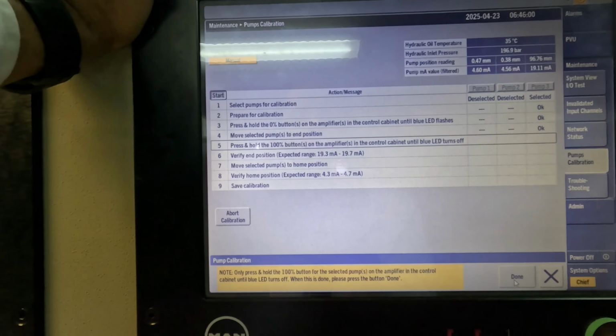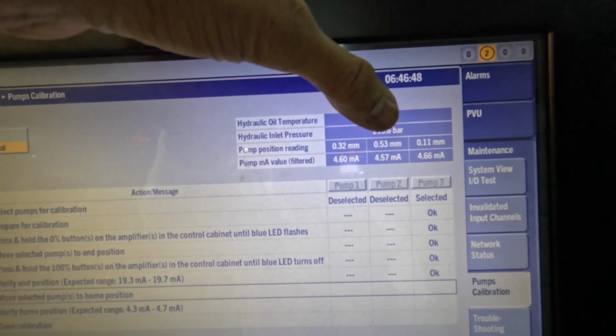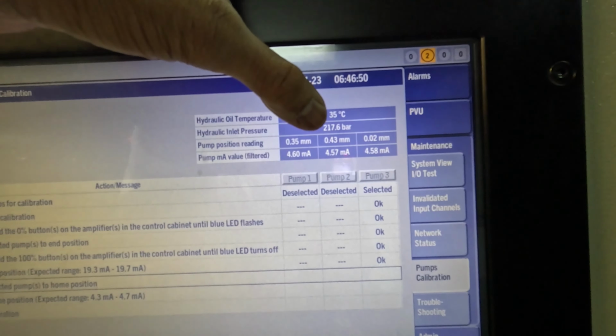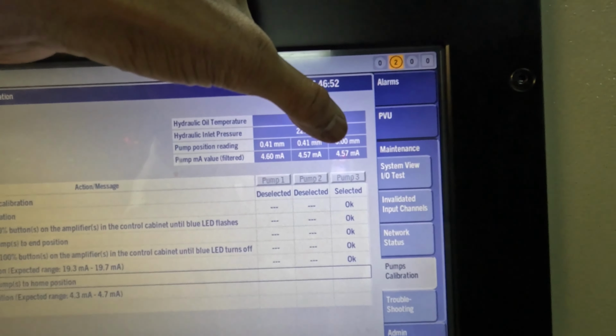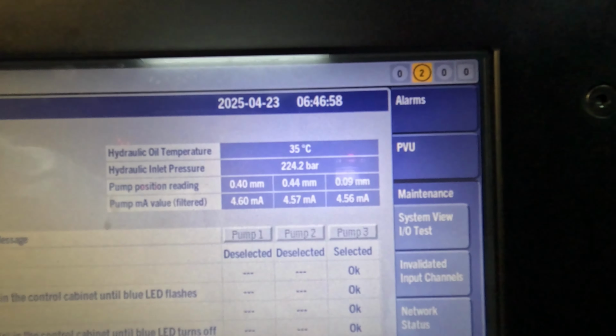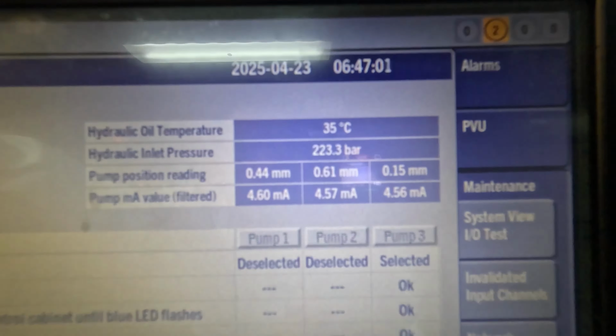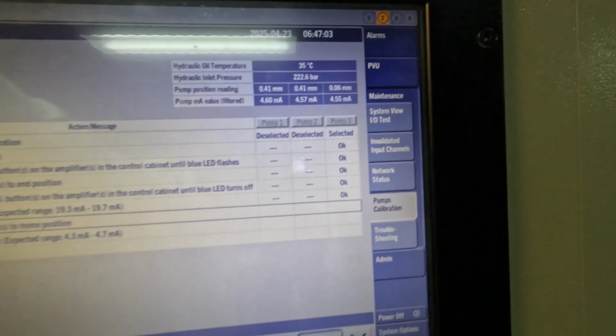Now it says move pump. Let's move the pump to the selected home position right now. These are the current values that we need to look at. This gives you the position of the pump, and right now we are at pump number 3. It reads 0.2 mm stroke and 4.56 milliamps. That means we are at the home position, so we have achieved our calibration. Now let's get these readings and then save the calibration.